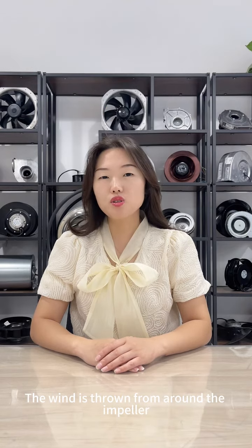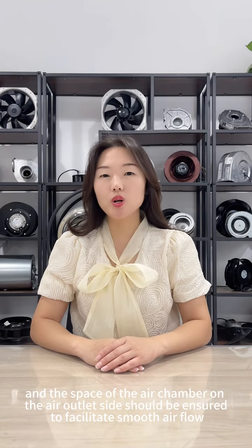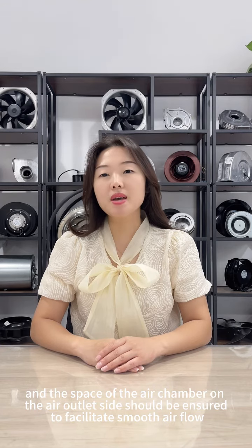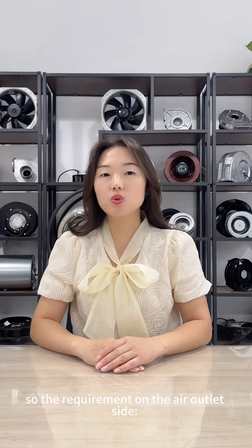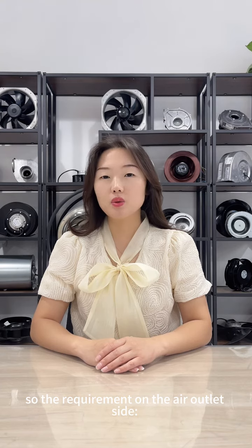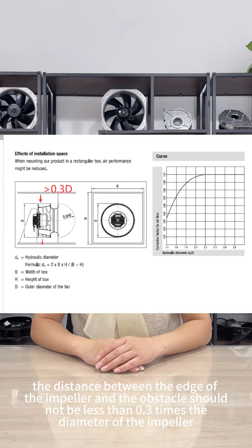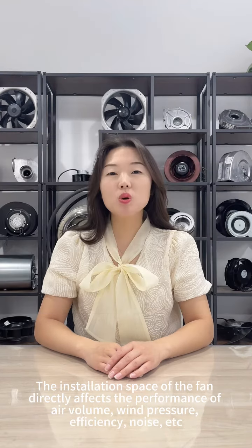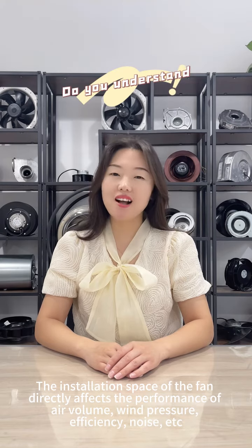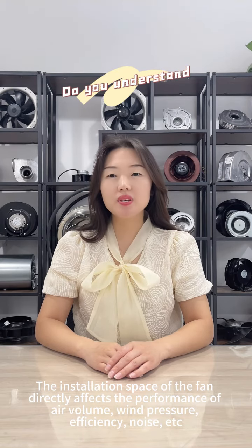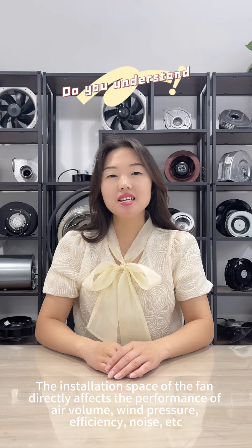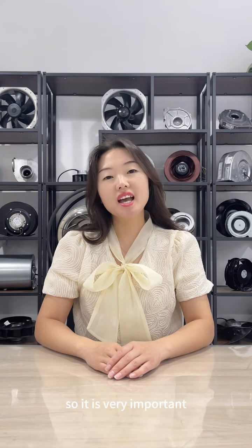The wind is thrown from around the impeller, and the space of the air chamber on the air outlet side should be ensured to facilitate smooth airflow. So the requirement on the air outlet side: the distance between the edge of the impeller and the obstacle should not be less than 0.3 times the diameter of the impeller. The installation space of the fan directly affects the performance of air volume, wind pressure, efficiency, noise, etc. So it is very important.